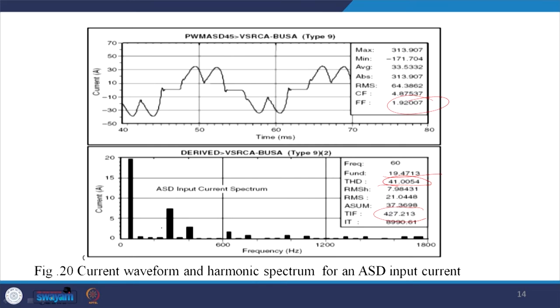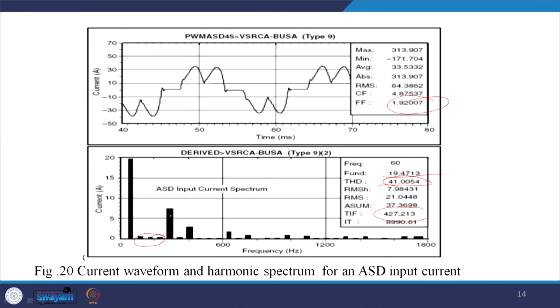The harmonic spectrum shows the fundamental, followed by components that come due to quantization error of sensors and are negligible. Essentially there is a fifth harmonic, a seventh harmonic, then the 11th and 13th harmonics, and so on. This is the harmonic spectrum for an adjustable speed drive.